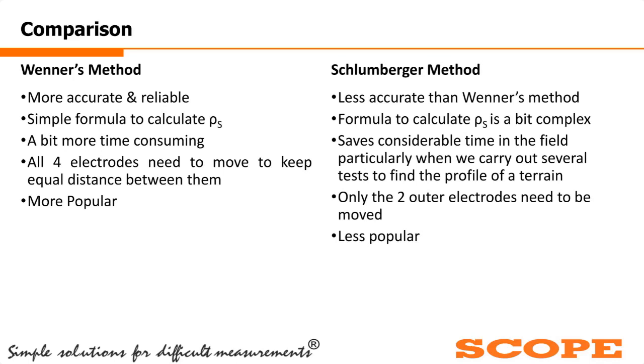And the next one is the Schlumberger method is less accurate as compared to Wenner's method. Generally, this Schlumberger method is used where there are limitations of the earth, where we have difficulty getting soil or earth surface nearby, because if there is any concrete type of surface nearby available, then due to this limitation of the earth surface, we will require this Schlumberger method. Then the next one, in this Schlumberger method, only two outer electrodes need to be moved. So the distance between the middle electrodes is fixed, and we only have to change the outer electrodes distance so that we can get multiple readings, and we can reach a conclusion of the earth resistivity measure.